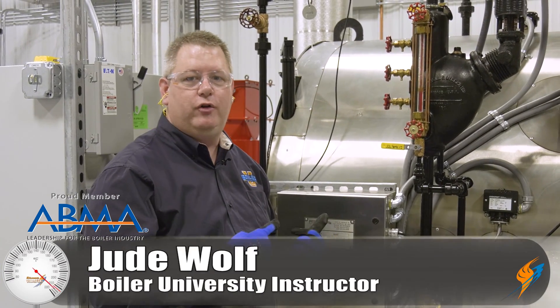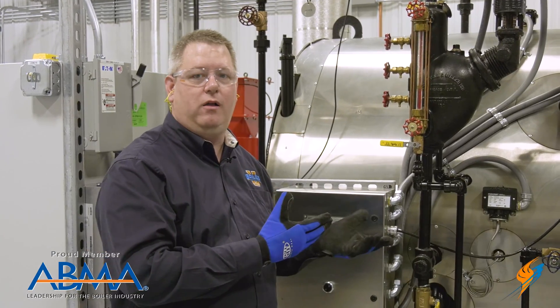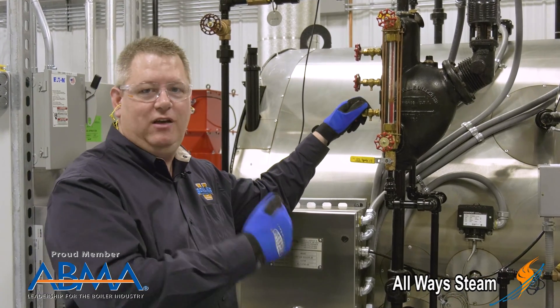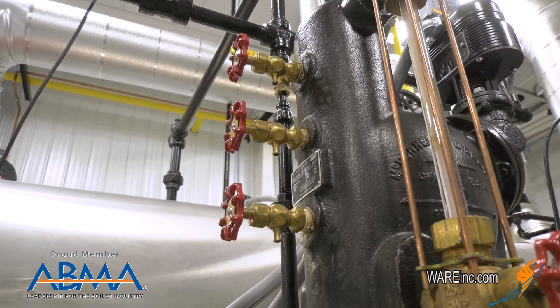Try-cocks are an important alternative to a sight glass if your sight glass is out of commission and you need to verify the water level in the boiler. Their location both above and below the water level can give you an indication, when open, of where the water level is. If we don't know the water level of the boiler it can be quite dangerous — if in doubt, we're going to shut the boiler down.